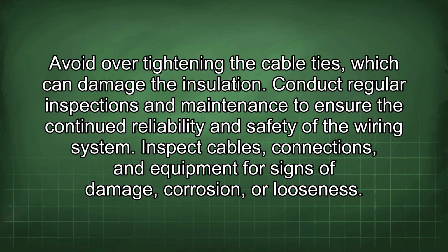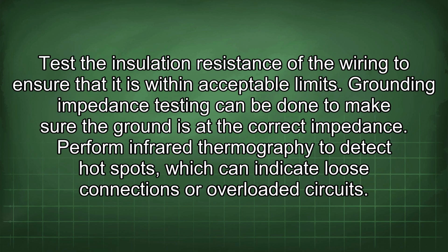Conduct regular inspections and maintenance to ensure the continued reliability and safety of the wiring system. Inspect cables, connections, and equipment for signs of damage, corrosion, or looseness. Test the insulation resistance of the wiring to ensure that it is within acceptable limits.